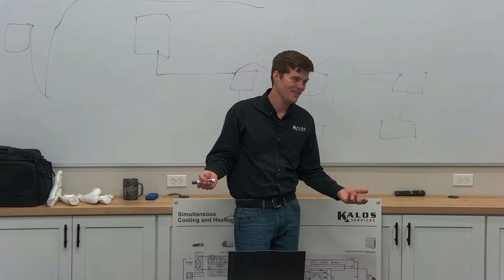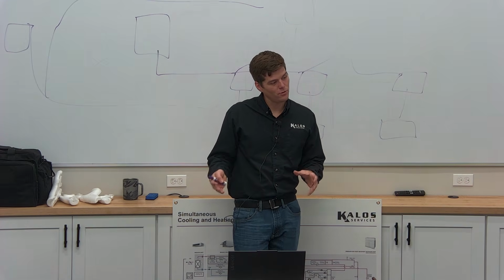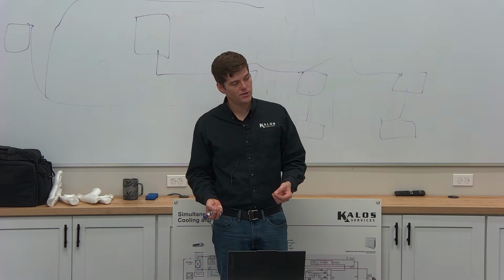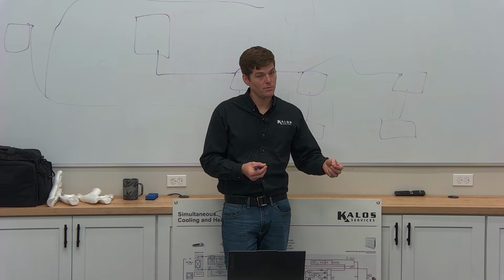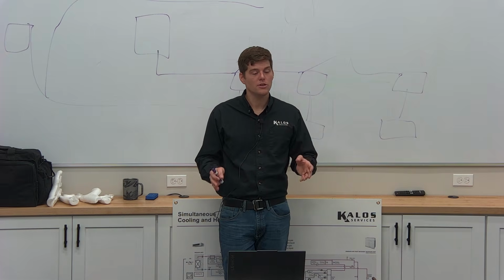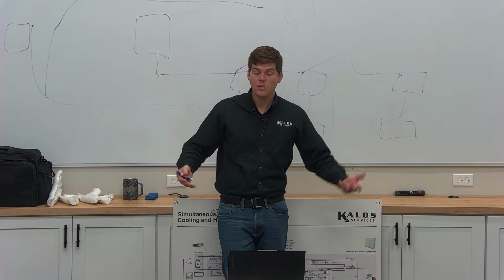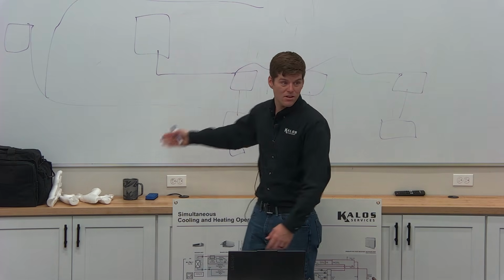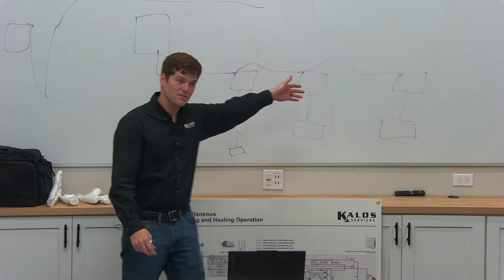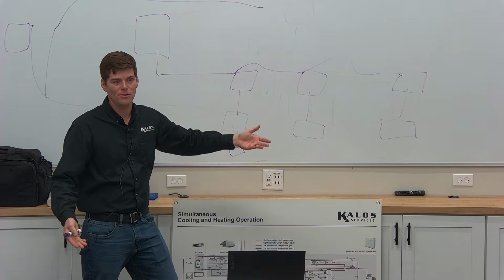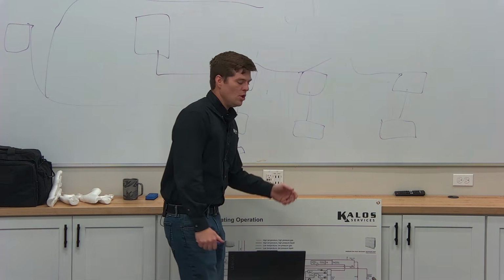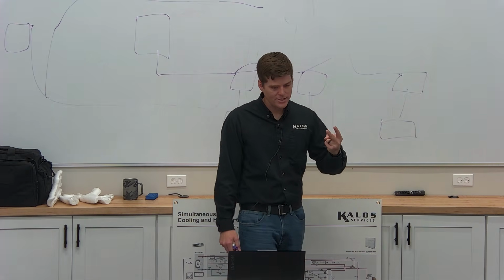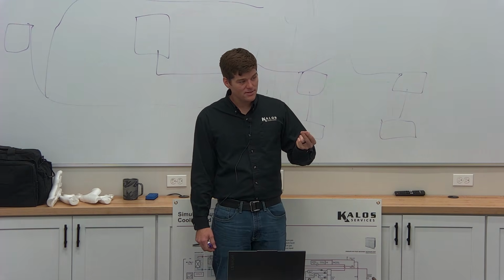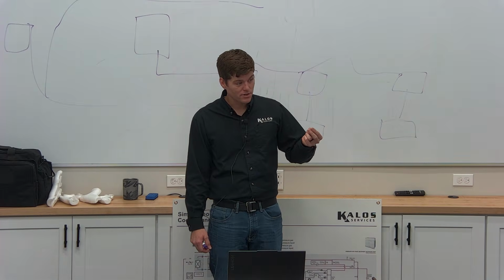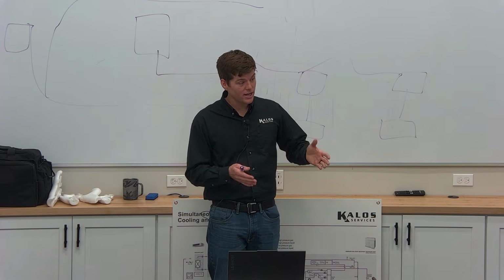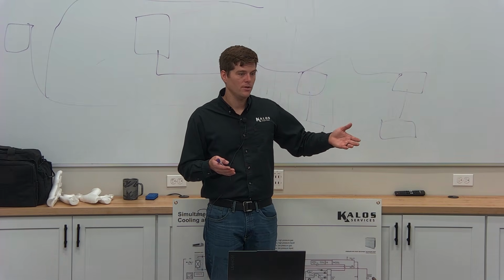It's ridiculous. The reason we don't use 24 volt control is there's too much information that has to be relayed in a timely manner between everybody at any given time to use that many wires. Your electrical panels will be the size of this board, full of ice cube relays to tell it to do something simple and menial. We use 2 wires because we transmit packets of data in binary code that the unit deciphers and understands exactly what it's saying and how.